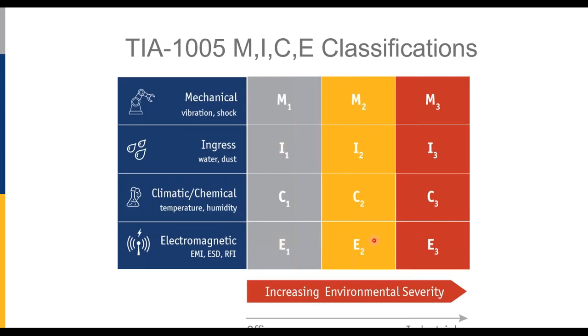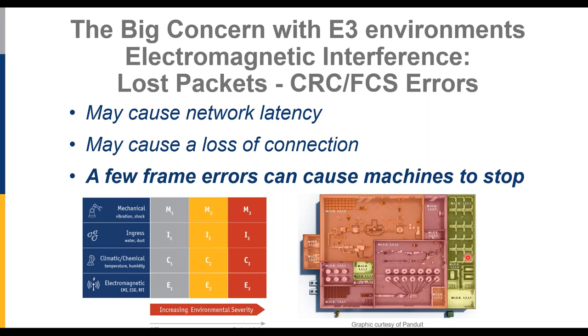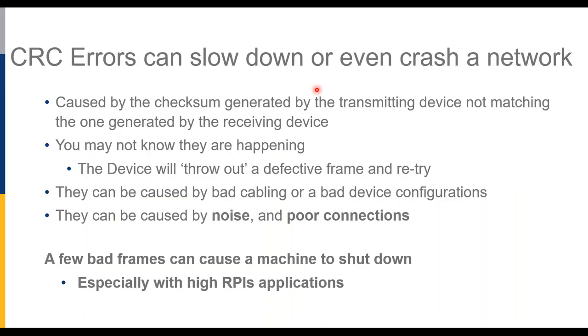Looking at the MICE chart, as you go from E1 to E2 to E3, you move to increasing environmental severity with more electromagnetic interference. What we worry about with that EMI are CRC and FCS errors — cyclical redundancy check or frame check sequence errors. These are caused by the checksum generated by the transmitting device not matching the one generated by the receiving device; a bit that was 'off' gets interference and arrives as 'on,' corrupting the frame.